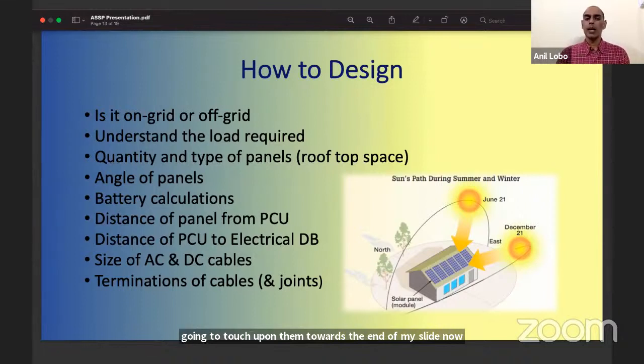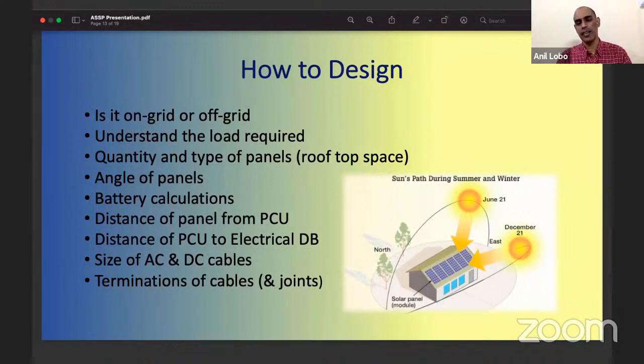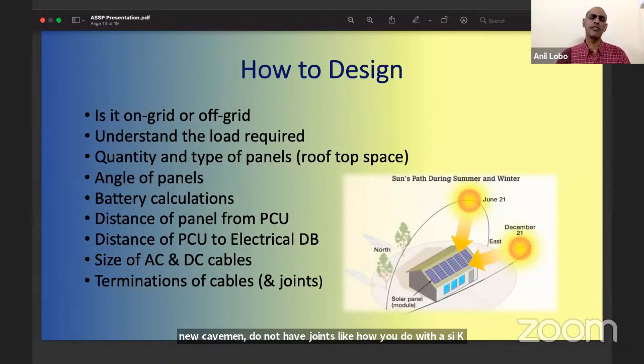Now, another very important part is the termination. You will not want to put joints, especially on the DC side. Any joint in your DC cable will cause the cable to overheat. And this overheating can have a cascading effect by lowering your energy available and also causing an electrical fire. So you want to avoid joints. If for some reason your cable has broken, you take the cable out and you put a new cable in. Do not have joints like how you would do with AC cables. And termination is very important.